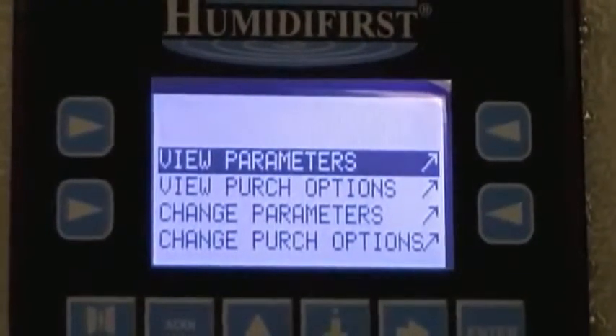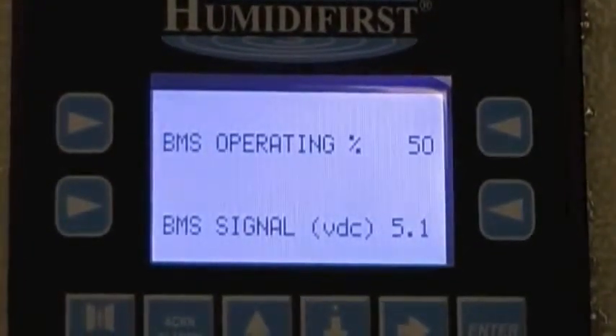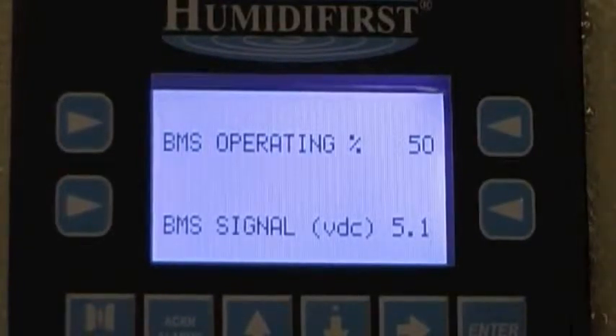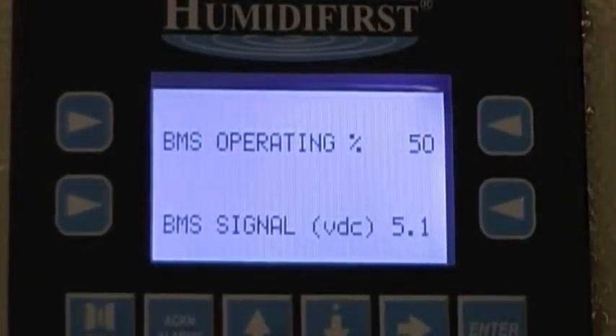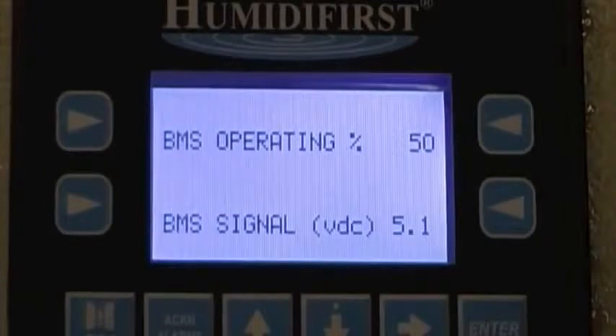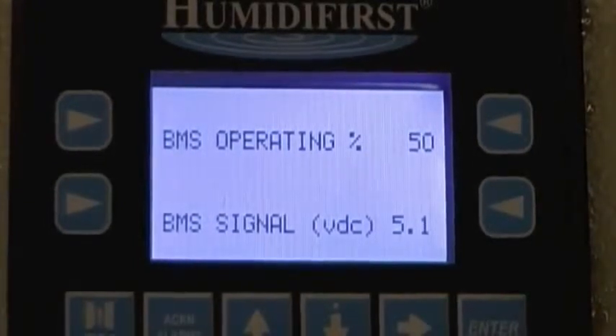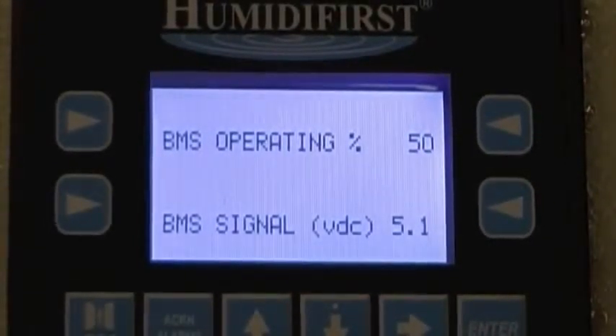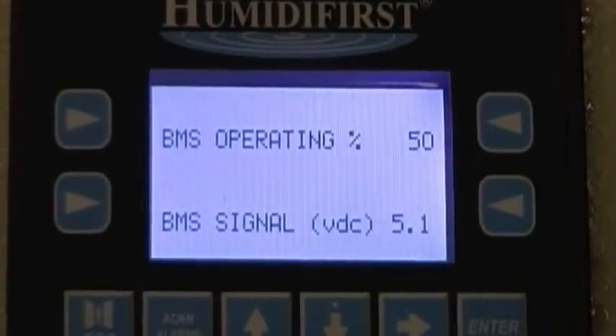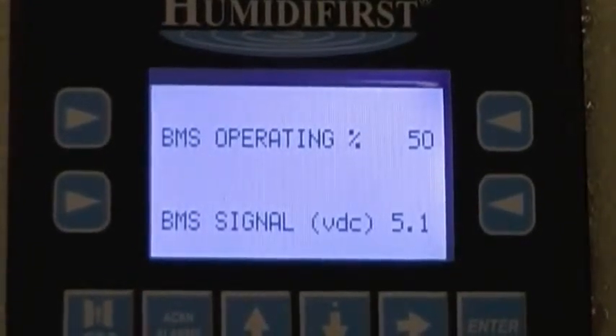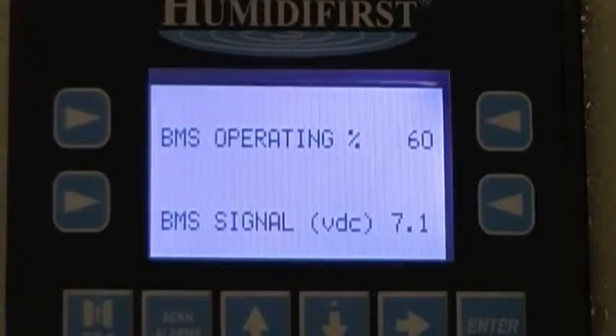Button number 3 is your BMS signal. This will show you your building management system signal from 0 to 10 VDC and the corresponding operating percent of the humidifiers. In this case, we have a BMS signal of 5.1 and our humidifiers are operating at 50%. Increasing the BMS signal will increase the operating percent of the humidifiers until 100% operation is reached at a BMS signal of 10.